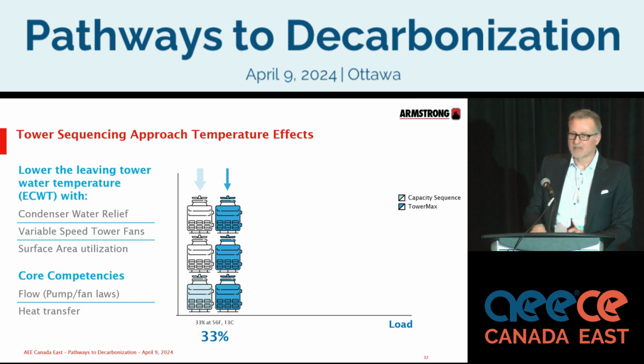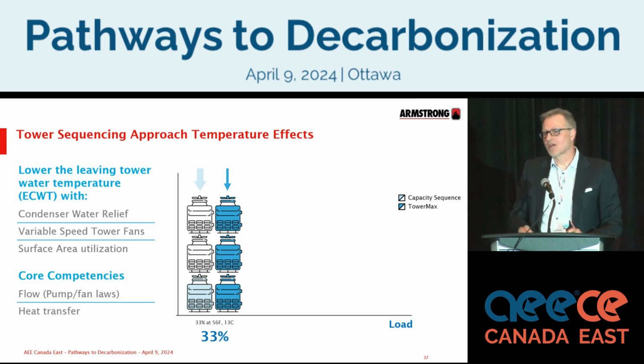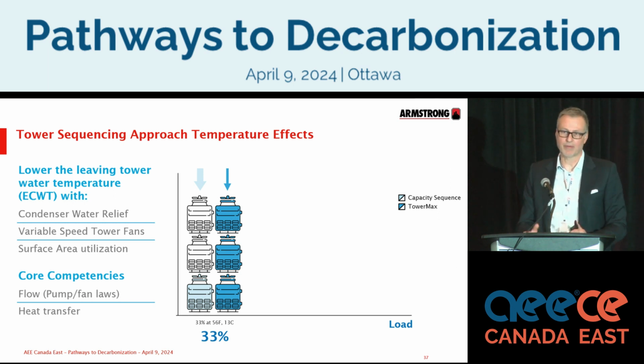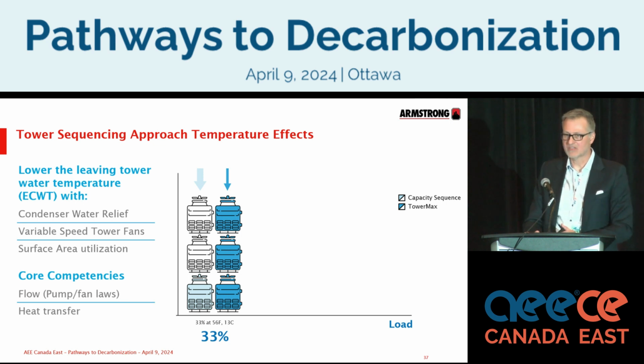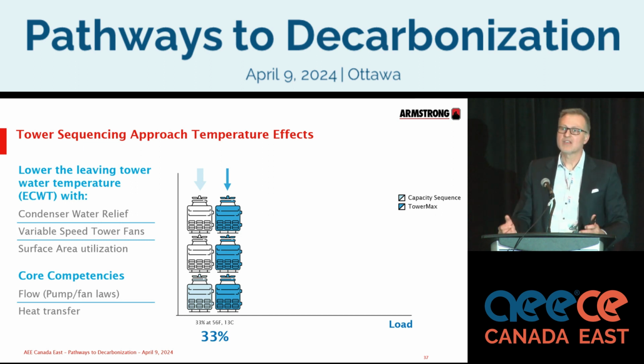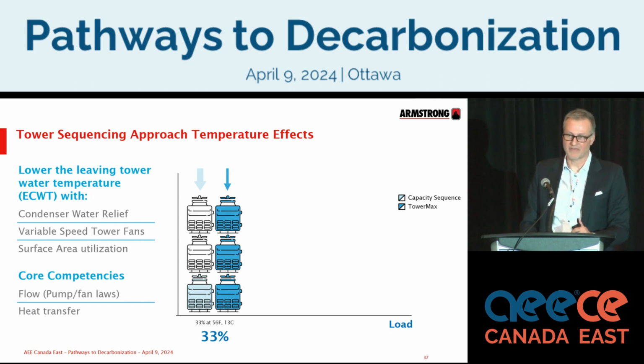What we're doing here is utilizing the tower's surface area that's available to us. So if we have 3 towers at part load, we will utilize all 3 towers. What happens then is that now that you've increased the surface area, you can drive down the fan speed. And remember the affinity laws: dropping down the speed of a piece of rotating equipment saves energy by the cube. So at 50% speed, you're saving about 70% of the power on that fan.